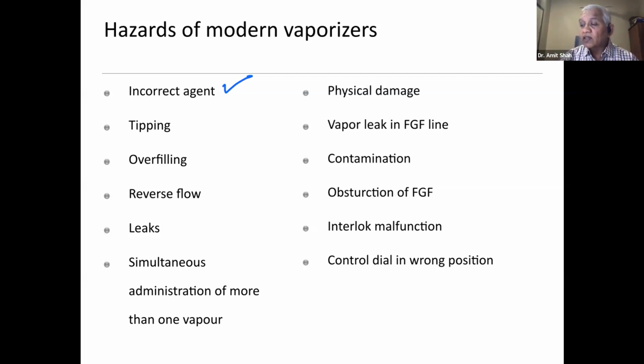You are not giving simultaneous administration of more than one vapor, but sometimes in the older anesthesia machines, if you have a back bar where you have mounted two, you can do it. Vapor leak, contamination, obstruction of fresh gas flow because of an improperly pushed vaporizer, interlock malfunctions. These are some of the problems which can occur even with your modern vaporizer. So you have to be extremely careful while using the vaporizer. And one of the most common hazards of a vaporizer is an empty vaporizer. You have to check every day in the morning when you come whether the vaporizer is completely filled or not. If you do not have an agent monitor, you will never know that the vaporizer has become empty and you're not giving any anesthetic agent. So an empty vaporizer is one of the most important problems which can occur.